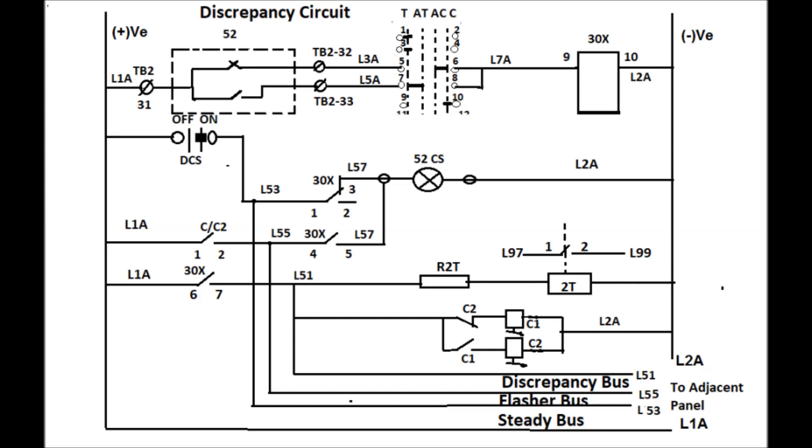Discrepancy bus will get through positive DC and also flasher relay will energize, and that will lead to energize the flasher bus. That is continuous on-off DC positive will go through the flasher bus wire, which will lead to flashing or blinking of the lamp in the said control switch of the panel.